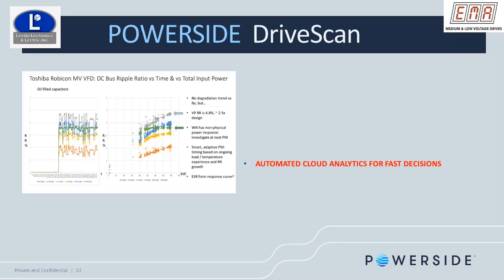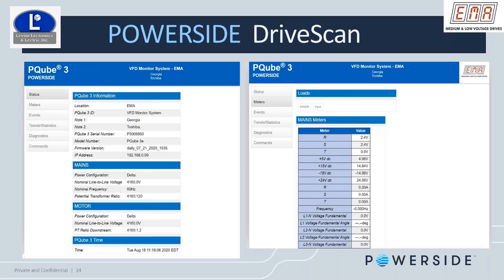So that's an indication that there may be a problem on this power module. If I set windows and limits on this drive, I would have gotten an email saying there's a problem on this power cell and you need to look at it and correct the problem. These are some of the things we can look at.